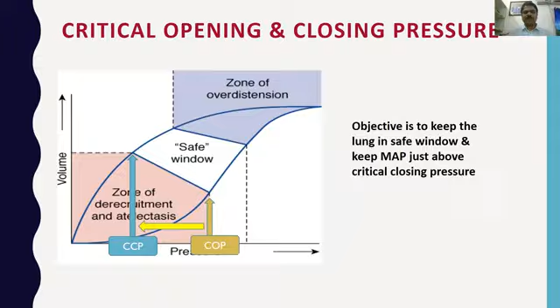After the lung is recruited, all the alveoli are recruited, if you keep the lung in the expiratory limb, you can get better volumes at a lesser pressure. As you can see here, at this particular point, the critical opening pressure, the pressure is more but the volume is less. But at the critical closing pressure, with a lesser pressure you are able to get more volume. This is a very important aspect you need to understand while doing a recruitment maneuver and while doing high frequency ventilation. That's what we do when you start high frequency ventilation. You recruit the lung and bring the lung into the expiratory phase of the PV loop, and there you need to operate.